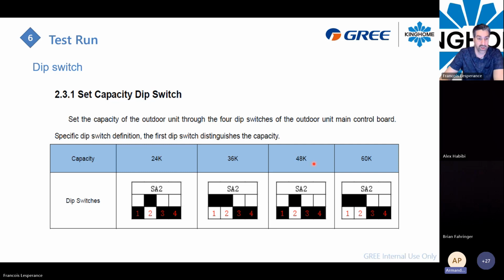And also, when we're adjusting, regardless of sizing, but adjusting eco mode or higher speed mode, whatever, do we then make an adjustment to our indoor fan speed? Regarding the static pressure you have. Yeah, so we would incorporate that adjustment as a 0.5 ton adjustment, and then adjust the indoor airflow accordingly. Okay, so that's the point. If you need, for example, 3.5 tons, you will have maybe 1400 CFM, around that.